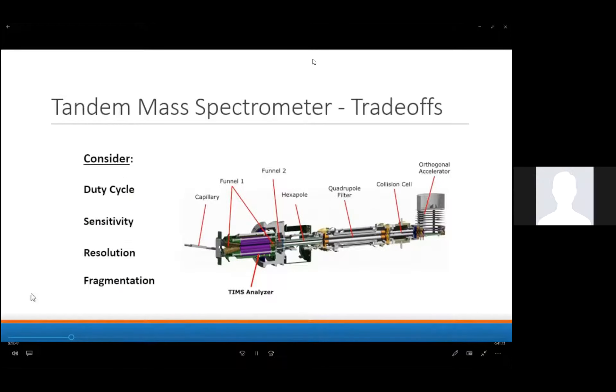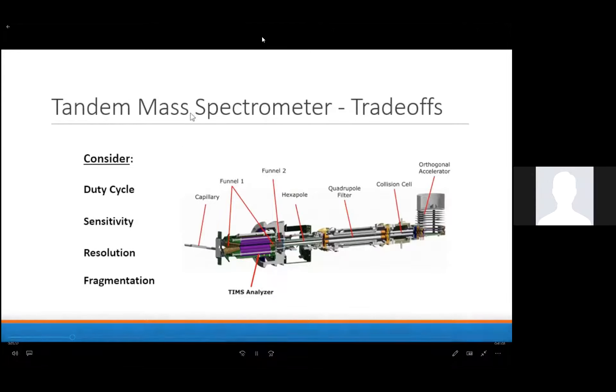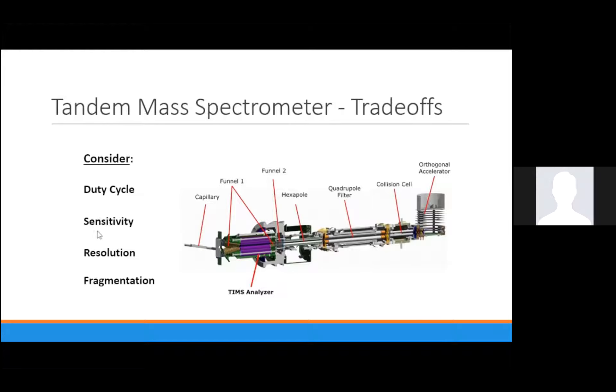There are of course trade-offs to be made with any tandem MS design. An instrument's duty cycle is pretty important, with higher duty cycles being able to capture more peaks from a constantly eluting LC. Sensitivity, resolution, and fragmentation are also very much worth considering. For example, the Timstof diagrammed here again, generally only fragments ions once, so it's not useful for higher MSN fragmentation.